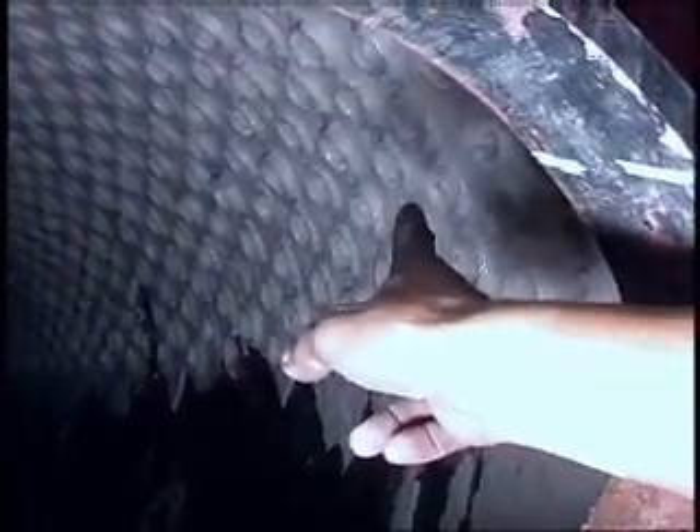During operational hours, this sludge is in suspension and some collapses at the bottom of the boiler and is flushed out by blow downing. In old boilers, after using Hydroflow for the first few months, a noticeable amount of hard scales will be found at the bottom of the boiler. This is due to scale layers being dissolved back into solution, forming crack lines. With the help of turbulence, the scale adhered to the pipe will come off.